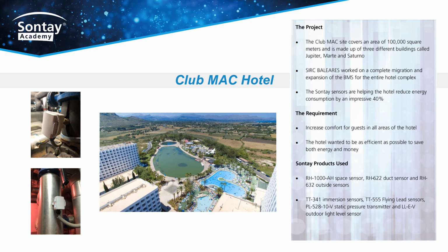The Sontay products used the relative humidity RH1000 AH space sensor, the duct RH622 sensors for RH, and the RH632 outside sensors. They also use TT341 immersion sensors, TT555 flying lead sensors, PL528 10V static pressure transmitter, and LLEV outdoor light level sensors. Hotels are an area where selecting the correct sensing technology presents a number of challenges.